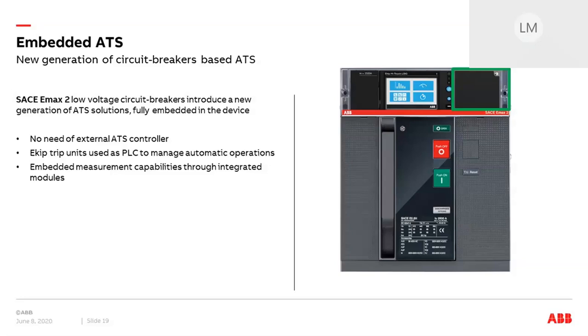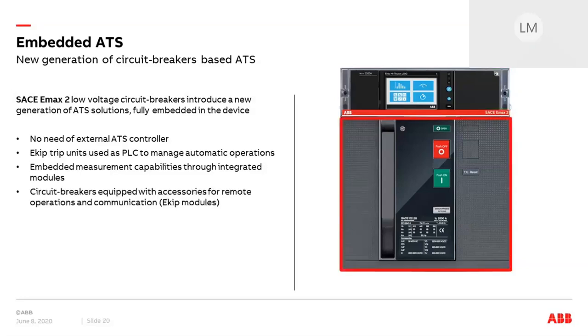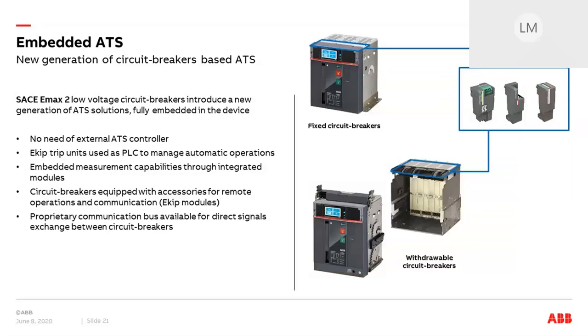EMAX2 circuit breakers offer what an external ATS controller typically does by directly monitoring power lines and ensuring detection of any faulty conditions. Thousands of parameters and statuses can be stored and digitally mapped in the trip units' memory to guarantee system integration, automatic operation, and remote control. From a hardware perspective, the circuit breakers must be equipped with all accessories needed for remote operations — like opening and closing coils, as well as the motor for remote spring charging. These accessories can be directly installed in the front of the circuit breaker, with the operating mechanism area fully segregated to ensure operator safety.